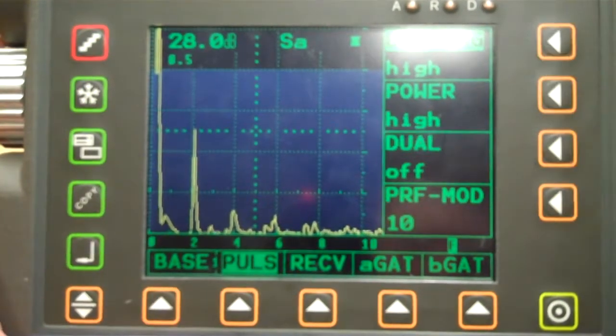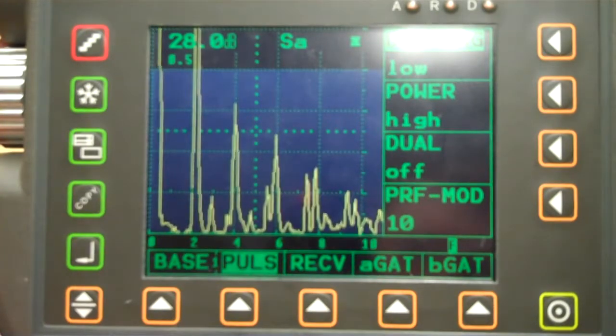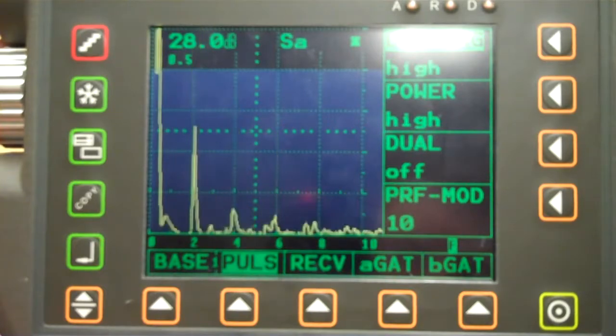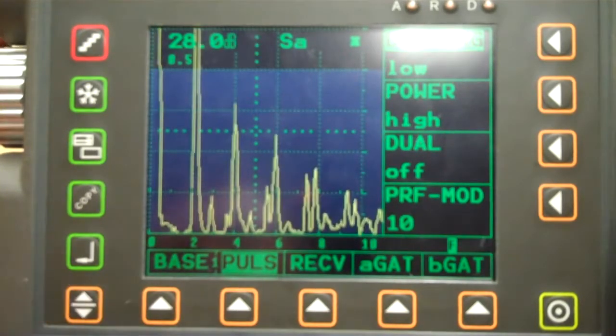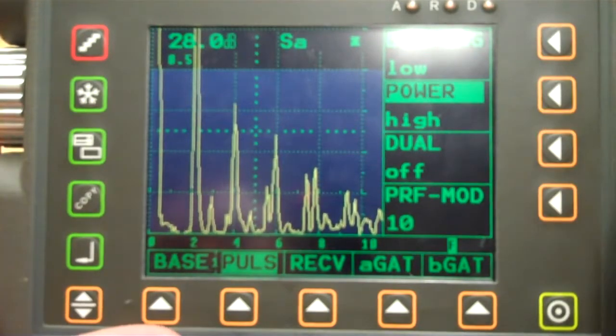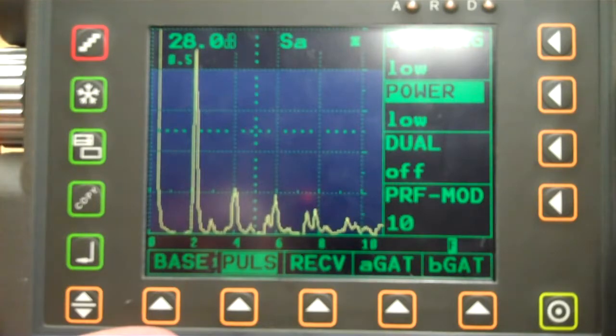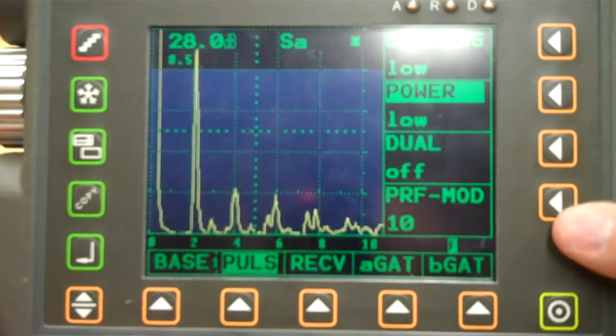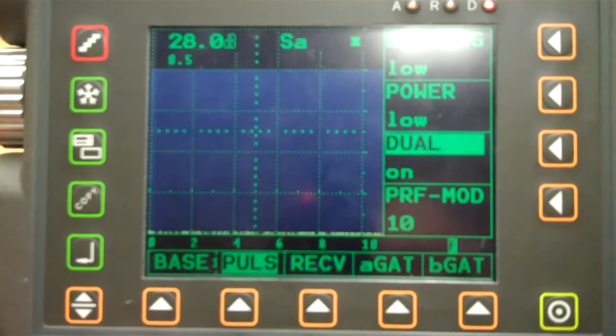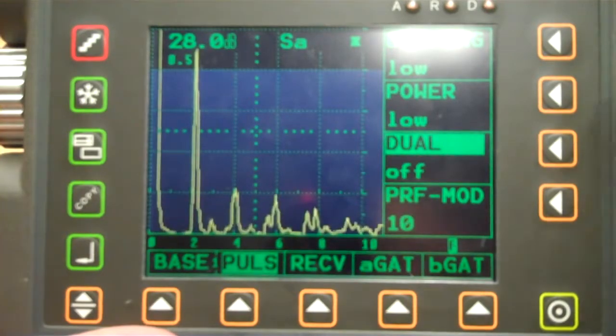Go to pulser. If I go high damping, I have that signal. If I go low damping, it's going to get bigger. Okay, as you can see, damping is just that. It dampens the signal. So there's high damping, low damping. Okay, so let's go low. High power, low power. High power, low power. So I'm going to say low power sounds good. Dual, if I turn the dual mode on, that's telling it I have a dual mode transducer, which I don't. So I want to leave that off.